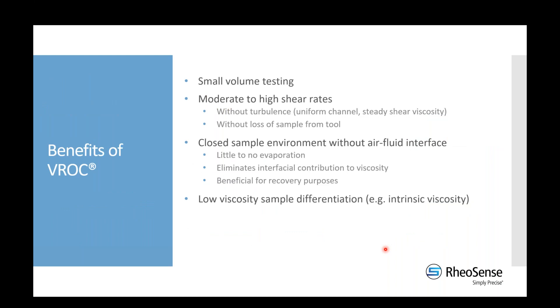Based on the nature of the microfluidics, it is small volume testing. Specific volumes depend on your test, but as a bare minimum, depending on the instrument, testing would require somewhere between about 15 and 26 microliters. You can get a certain amount of data from that, but because of the flow-through design, you'll need more volume if you're trying to reach maximum shear rates. Overall it tends to be smaller volume than using rotational tools.